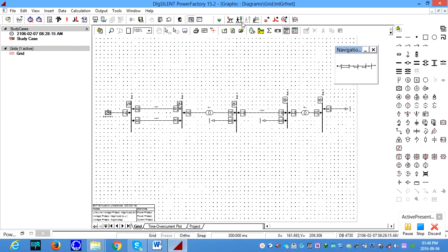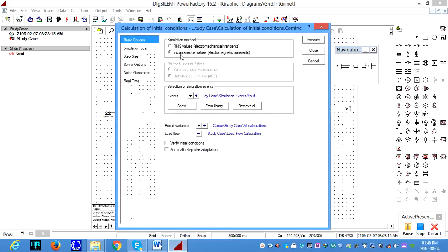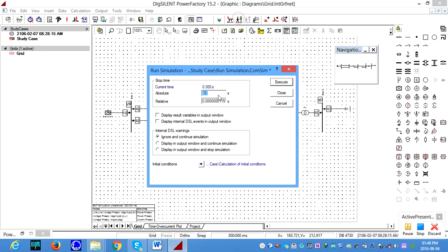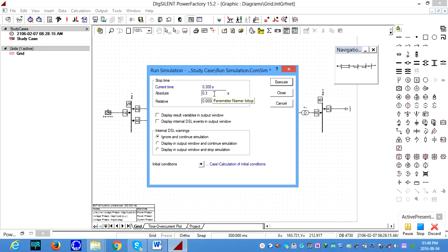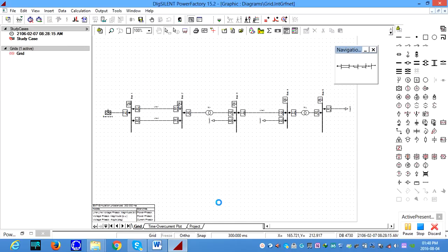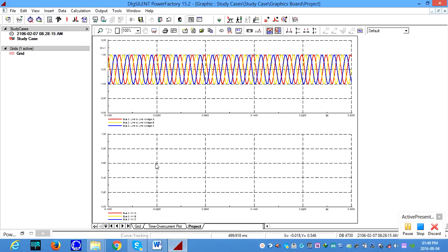Now we need to go to the simulation and make sure your simulation method is instantaneous. If it is RMS, we'll get a straight line. Okay. And go to the simulation. So for our total time, we need to include a time greater than 0.4 seconds because our ground fault is clearing at 0.4 seconds. So let's say 0.5 seconds and run the simulation.